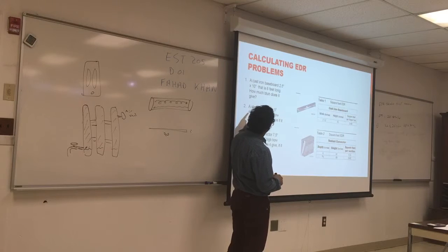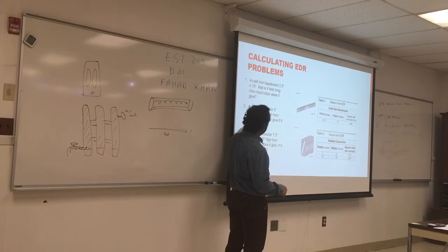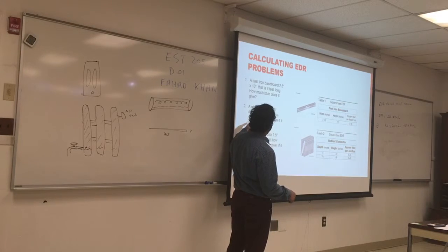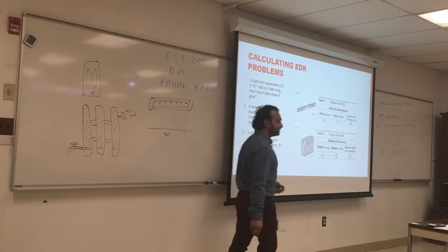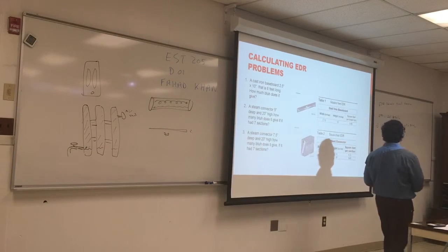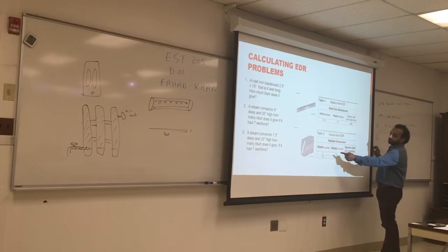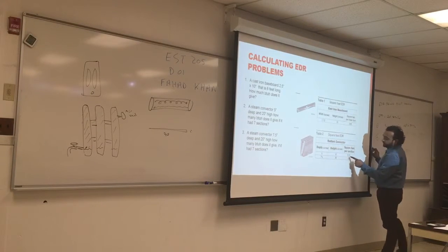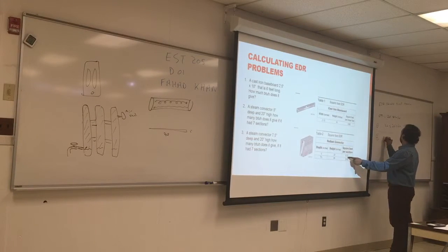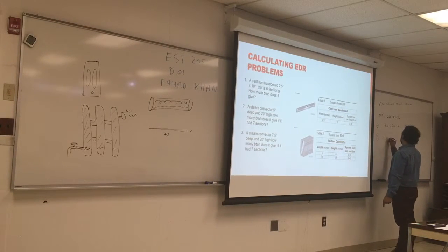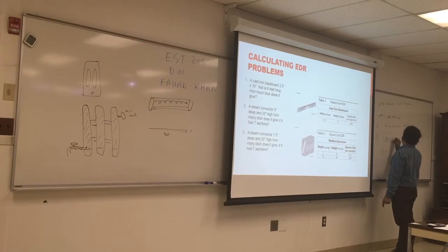So this is another convector. Those are called convectors. 5 inches by 20, so this is 5 by 20. Look at the dimensions, and they give you the EDR. So how much EDR, how many BTU, get out of that? So I look up the radiator, 5 by 20. It will give me 2.25 times 240.